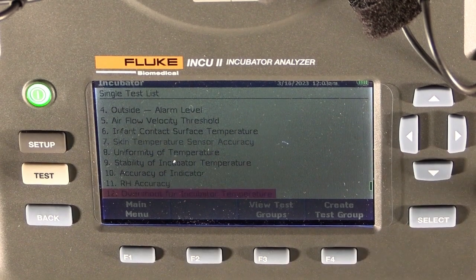Step 12, the overshoot for incubator temperature. During warm-up, it will overshoot the set temperature and then return back to its set temperature. That overshoot should not go higher than 38 degrees Celsius. So we want to make sure that it does not exceed that, because that is not good for your baby.